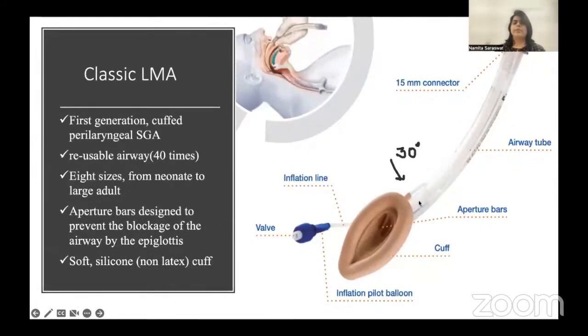This is an airway tube and this is a mask. There's a 15 mm universal connector. The angle which is formed between the airway tube and the mask is 30 degrees. And there's an inflation line, pilot balloon, and a valve. These are the aperture bars, which will prevent the epiglottis from causing any obstruction in the airway. This is made up of a soft silicone, non-latex cuff.